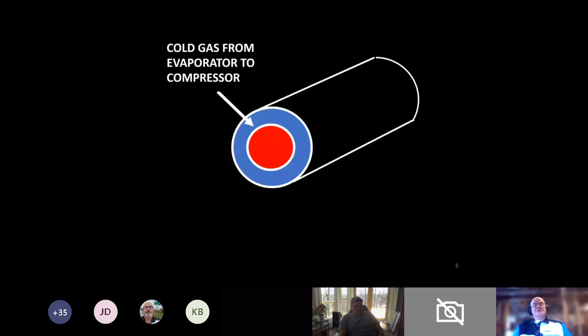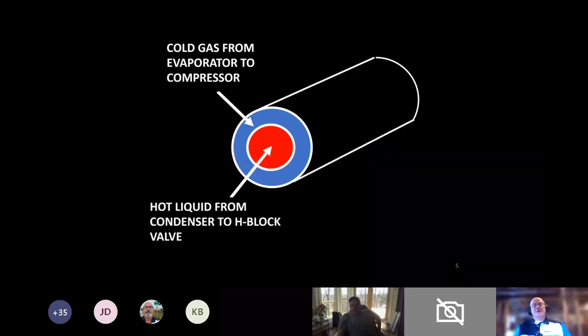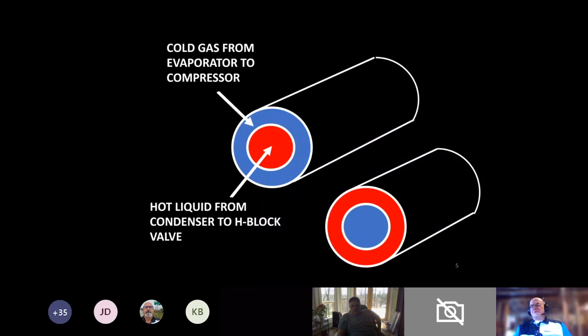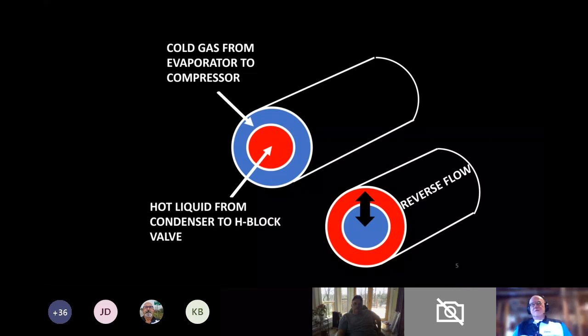Okay, so this is a graphic cutaway: cold gas from the evaporator to the compressor in this case, and of course the hot liquid from the condenser to the H block valve. This one has the high side flowing on the inside and the low side on the outside. It can be reversed, reverse flow depending on the OEM preference. They're usually insulated with some type of insulation. It could be a braid or rubber. It's not just bare metal on the outside.